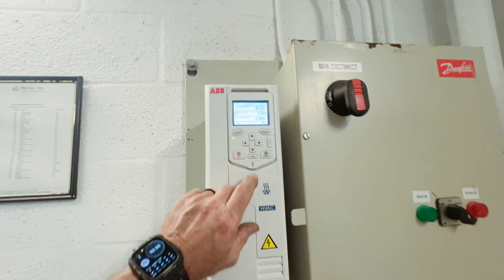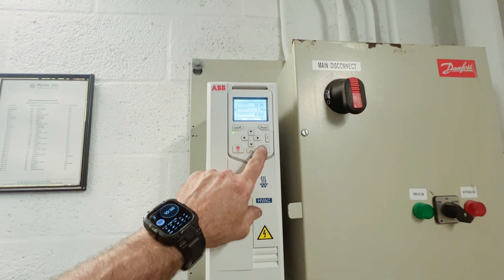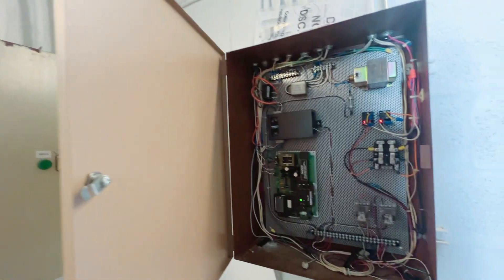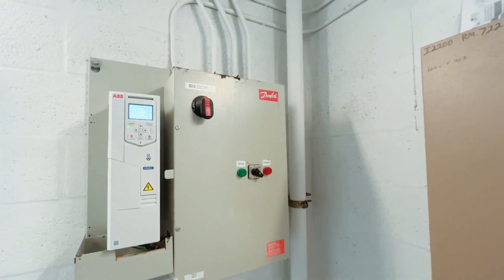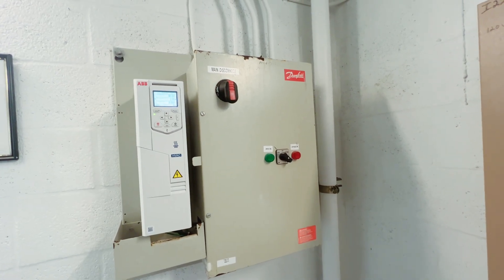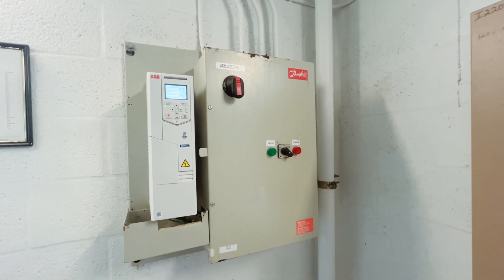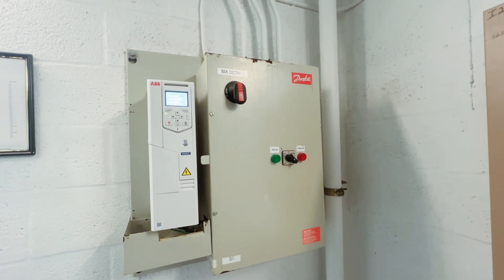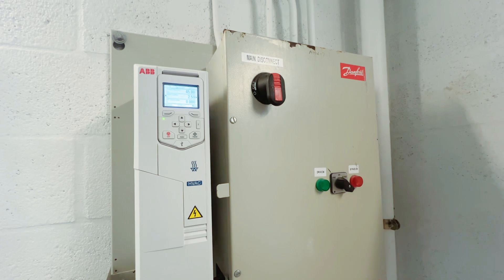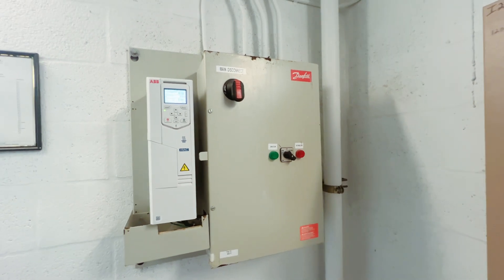Let's see if we got reloaded — negative, they must have put me at the end of the day list, so back to hand we go. We'll leave it there in hand. Once they replace the other controller it should go back to automatic, and the new valve is already installed so once they restore the controls it should take off and do its thing. Unfortunately we had a casualty in the chiller plant and need to replace another motor. This place is haunted with power failures — they still have not done our fuse disconnects. Anyway, thanks for watching, catch you next video.